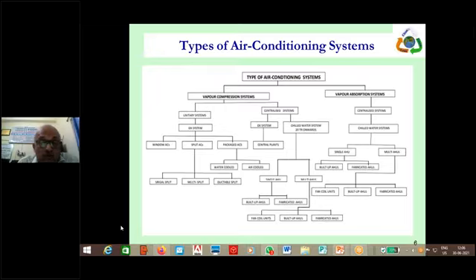For smaller plants, we can have direct expansion, and where we have large systems, we need more, or due to certain reasons where you cannot have the system, they go for a chilled water system, where the refrigerant system produces the chilled water, and the chilled water is circulated through the air handling units or small fan coil units. So one part is producing the fluid which will cool the air or which will condition the air. Another part is then supplying that chilled cool air into the premises.